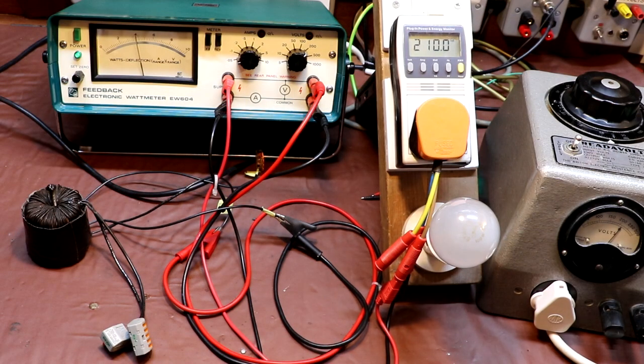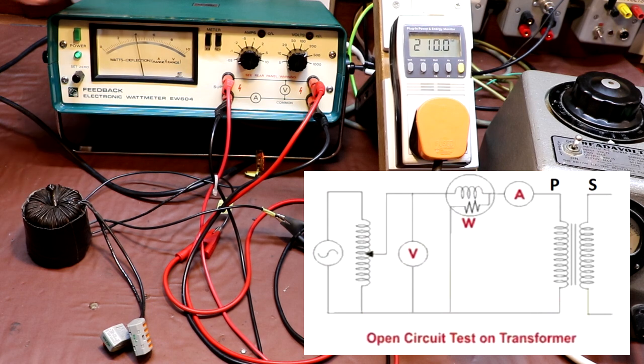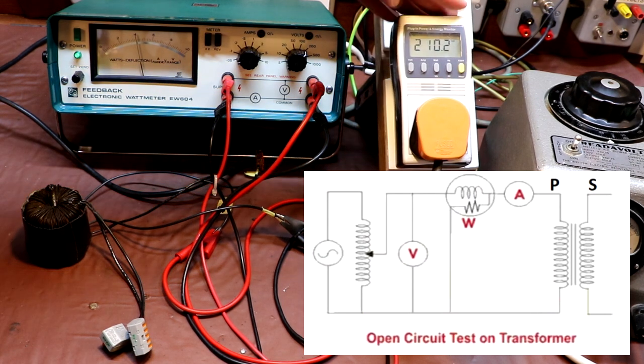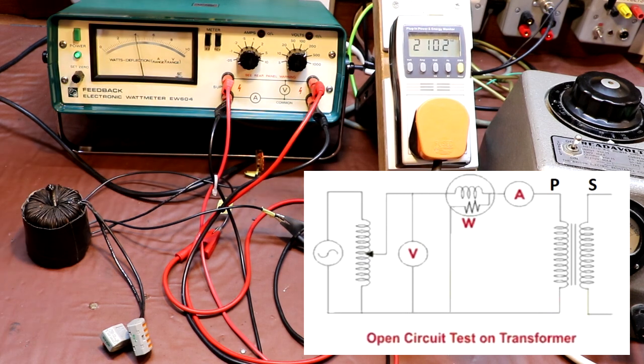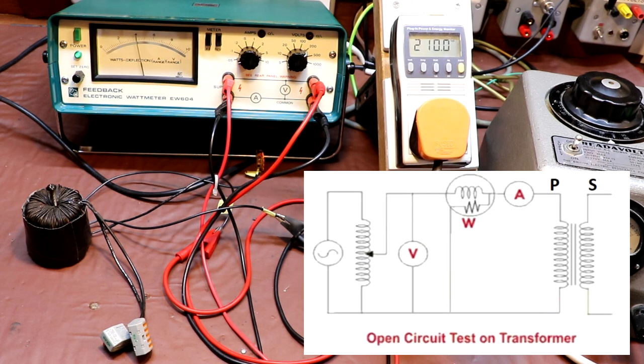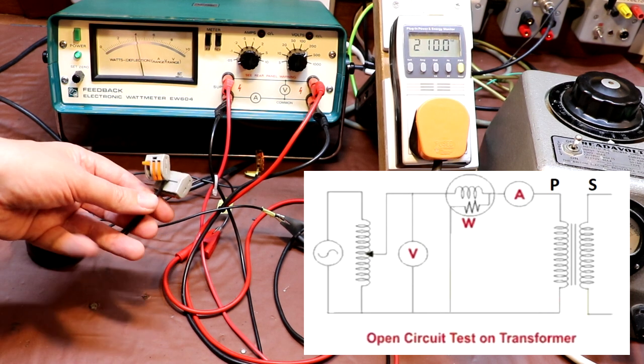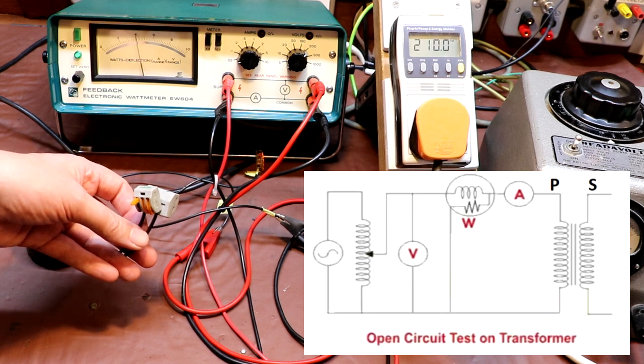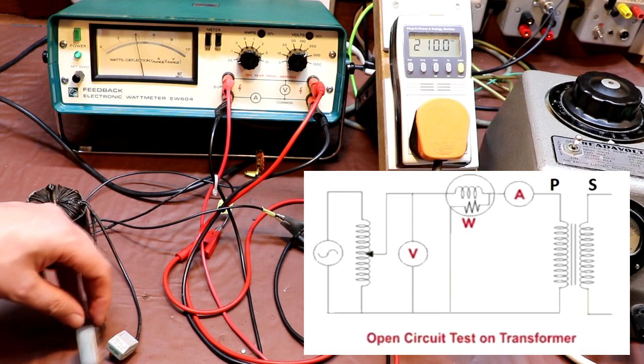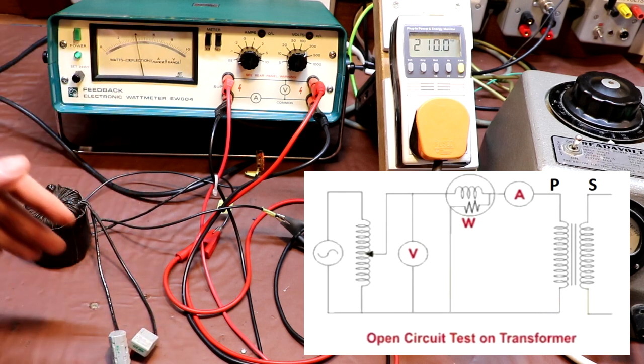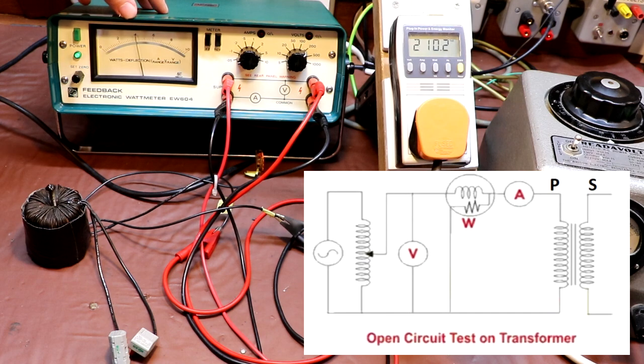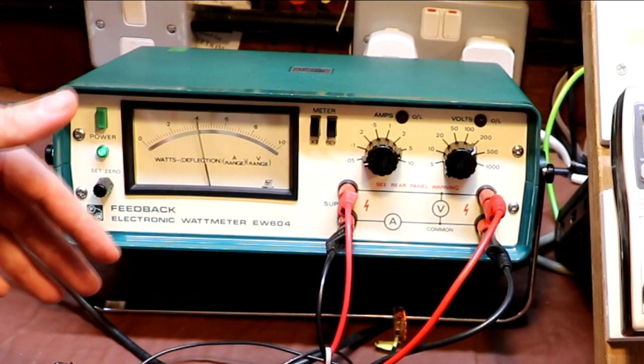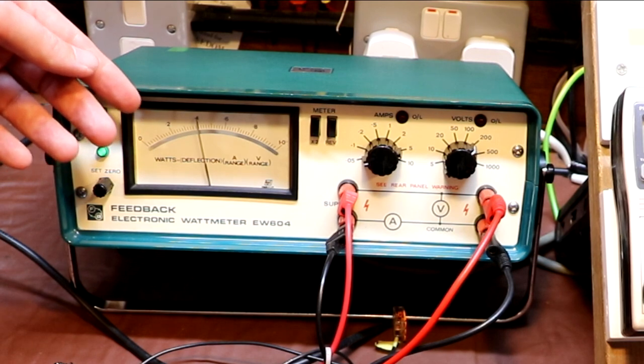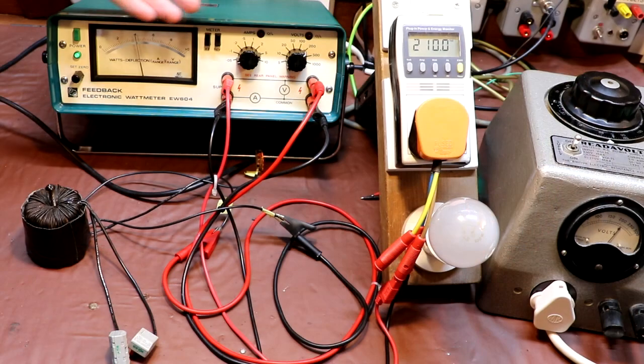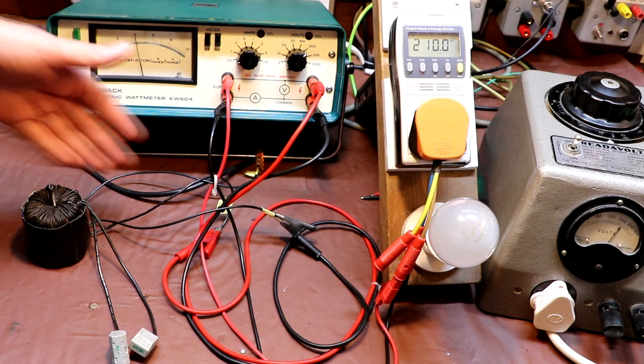So I'm going to repeat our core loss test again, and I'm going to use the feedback meter to measure the power as opposed to this wall wart power meter, which is inaccurate. This particular test is known as the open circuit test, and the reason it's called that is because the output terminals of the transformer are open circuit, we've got nothing connected to them. So at the moment the transformer is not delivering any useful power, but if we look at the indication on the power meter, it's consuming 4 watts of power. So the transformer's consuming 4 watts of power but outputting none.